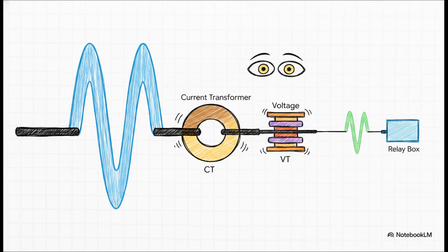You've got current transformers, or CTs, which step down the massive primary currents flowing through the lines, and voltage transformers, VTs, stepping down the extreme high voltages. They deliver safe secondary signals, usually around 1 amp or 5 amps, right to the relays. But remember this, the relay's logic is only ever as good as the signal it gets from these transformers.